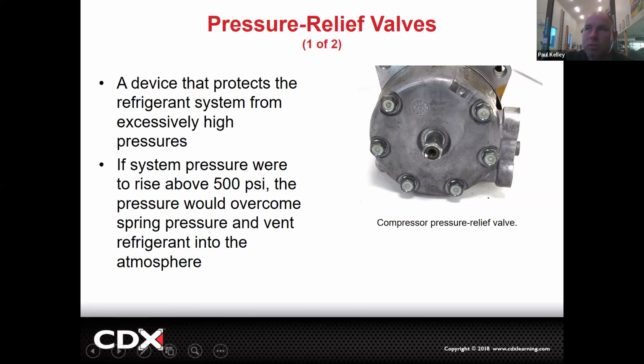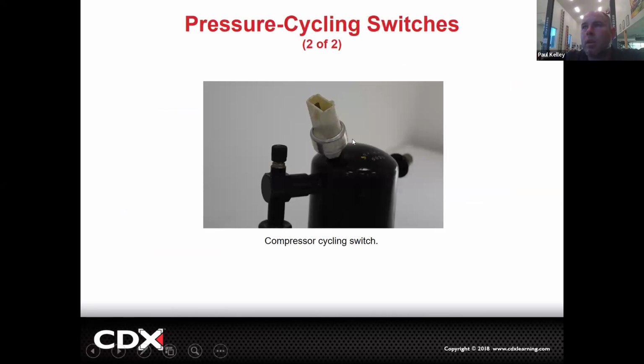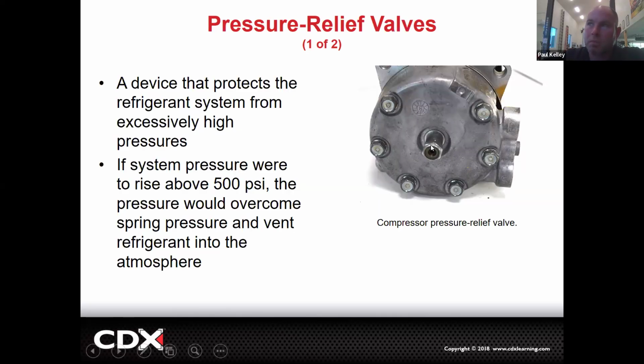You know the problem though? It shoots refrigerant and oil and possibly dye all over the compressor. Then you're thinking the compressor's leaking, right? And then come to find out somebody overcharged it. It blew oil and dye everywhere a few times until it was no longer overcharged and now it's fine, right? So you all need to know on the compressor, for protection of the compressor, it does have a type of blow-off valve, a PRD, if you will, pressure relief device, pressure relief valve. Cool. So a lot of times it's 500 PSI though. We really should not be seeing 500 PSI. And if we do, something's wrong. Am I right? This is purely mechanical. It's just a spring and seat.